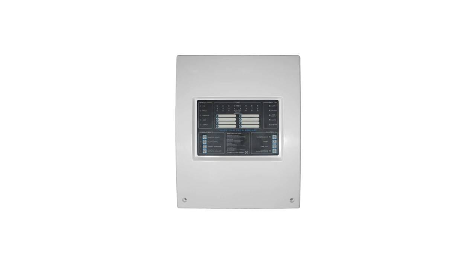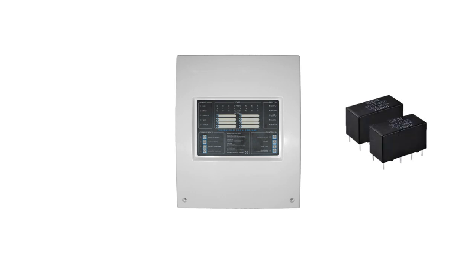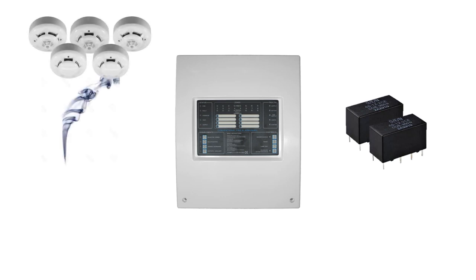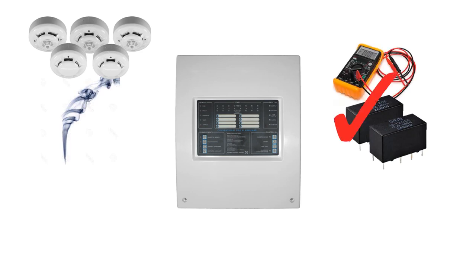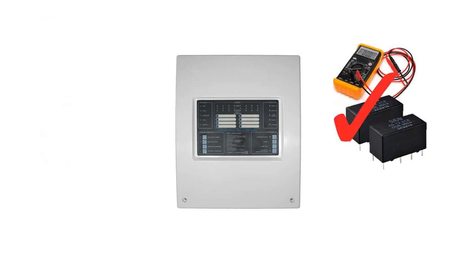The final steps in the commissioning process are to check the operation of other equipment connected to the panel. Specific requirements will depend on what equipment is connected. However, the operation of the fire alarm and fault output relays can be checked. To check the operation of the fire alarm relays, activate a detector and monitor the relay output for operation. Reset the control panel and check that the relay also resets.